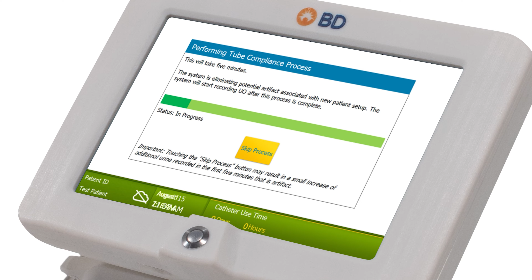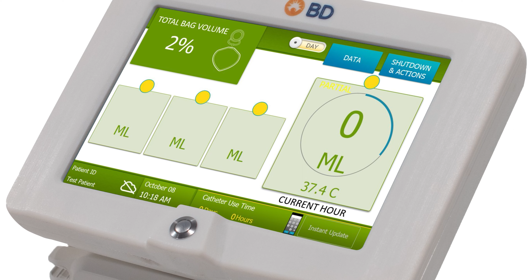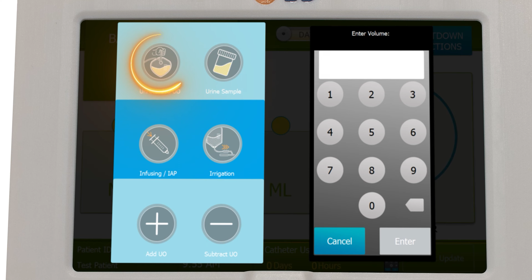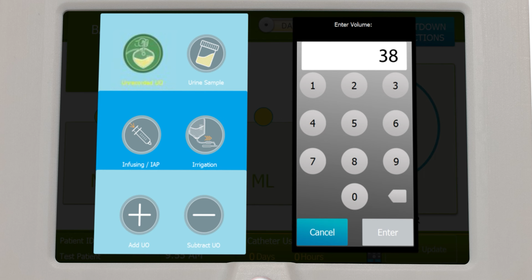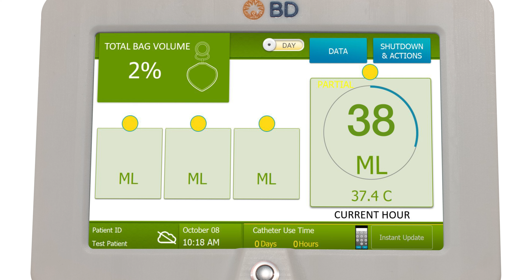However, skipping the process may cause the system to record a small amount of urine in the first 5 minutes that is actually artifact. Note that the initial screen for a new patient starts with the current hour at 0 milliliters. To add urine already collected in the bag for the current hour, simply touch the calculator icon. Then press the Unrecorded UO button. Estimate the amount of urine already in the bag and type it into the calculator, then touch Enter. Now the current hour box will show what has been collected for the first hour of monitoring.